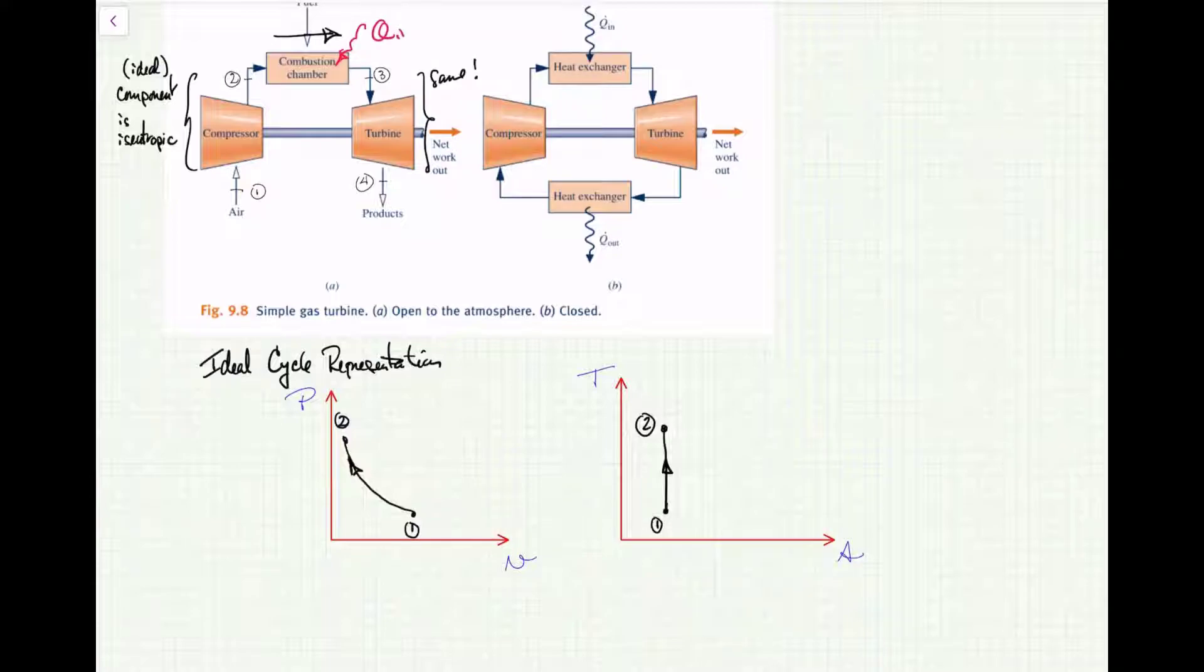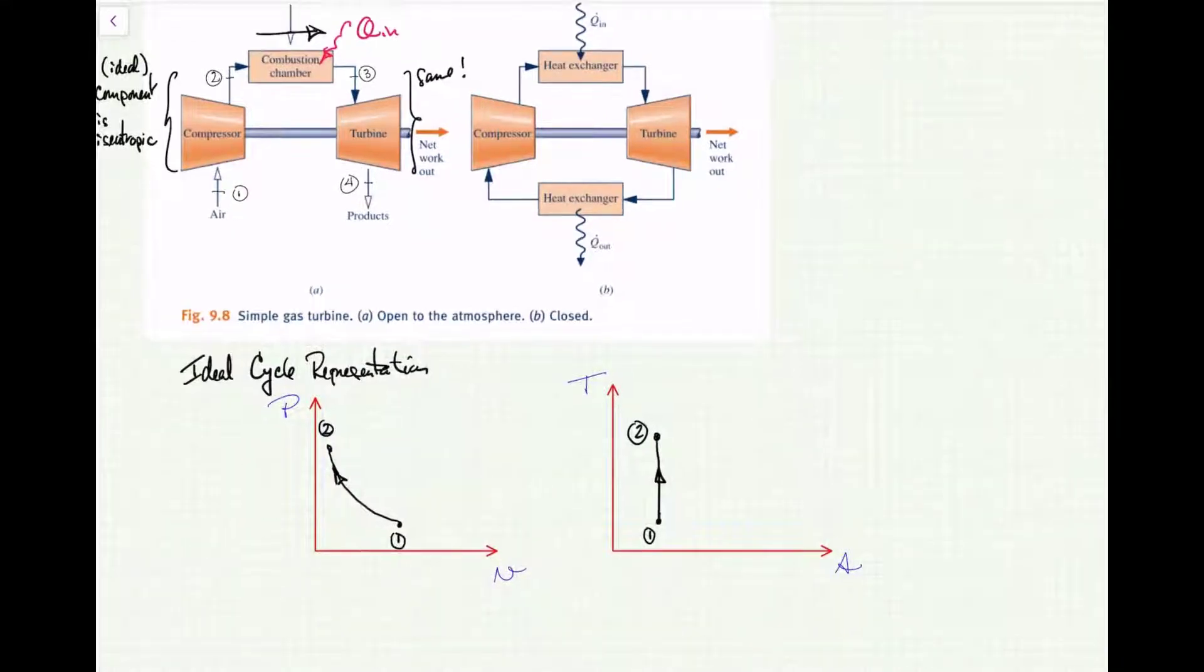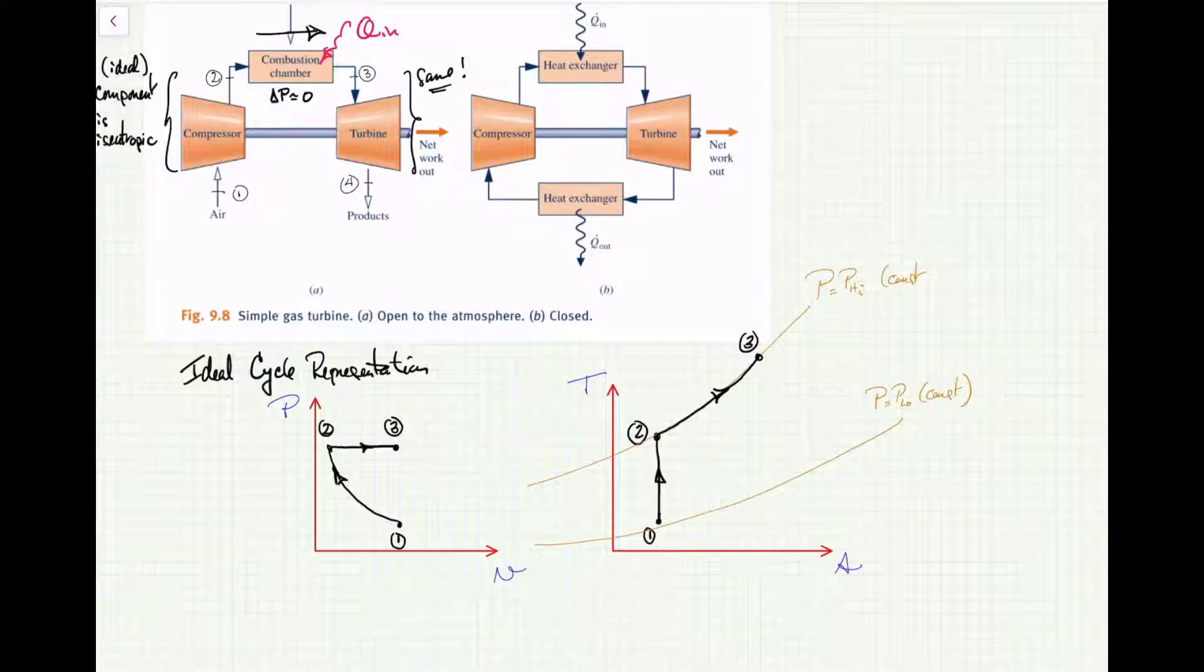Next we're adding heat through the combustion chamber, Q_in, and that's going to move us at constant pressure from point 2 to point 3. The gas turbine cycle in the ideal representation has a lossless, pressure-lossless combustion chamber where the flow gets heat added to it without decreasing pressure—so a horizontal line, like a diesel cycle. On a T-S diagram, this follows the isobar, which are these divergent curves for an ideal gas, from 2 to 3.